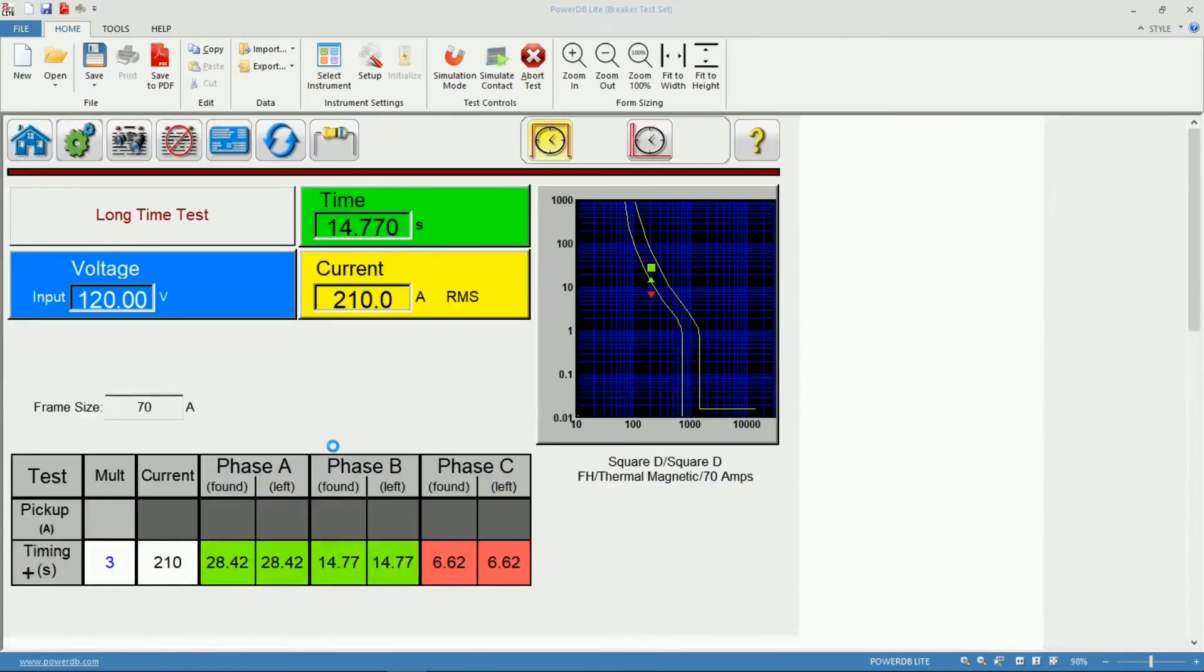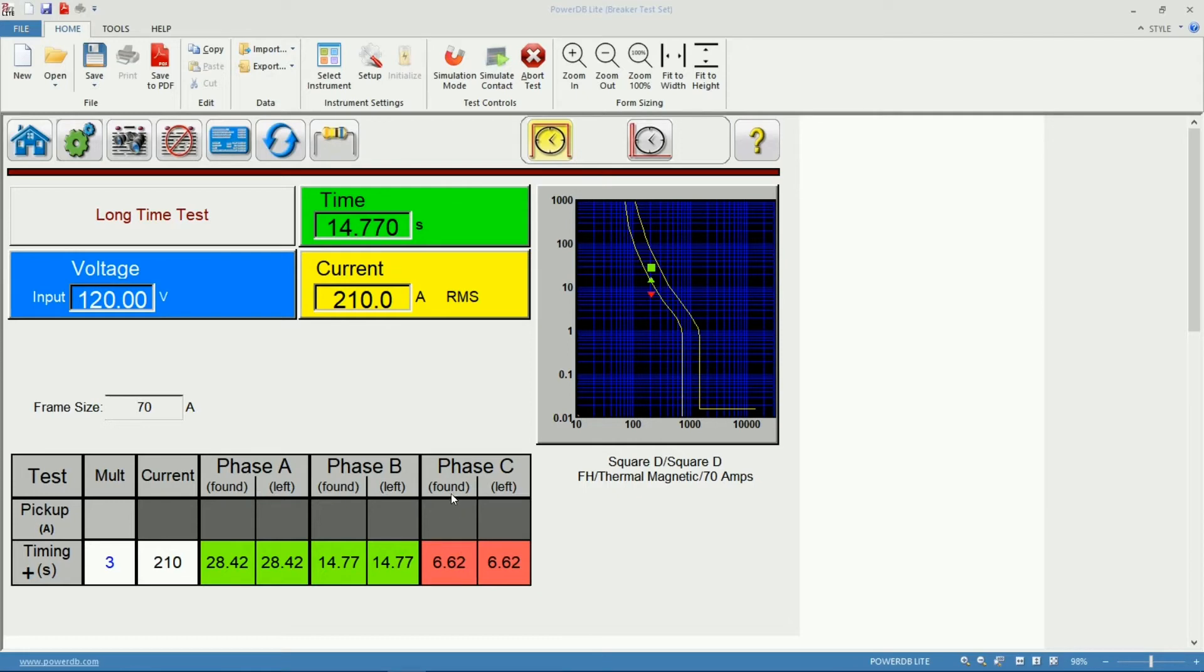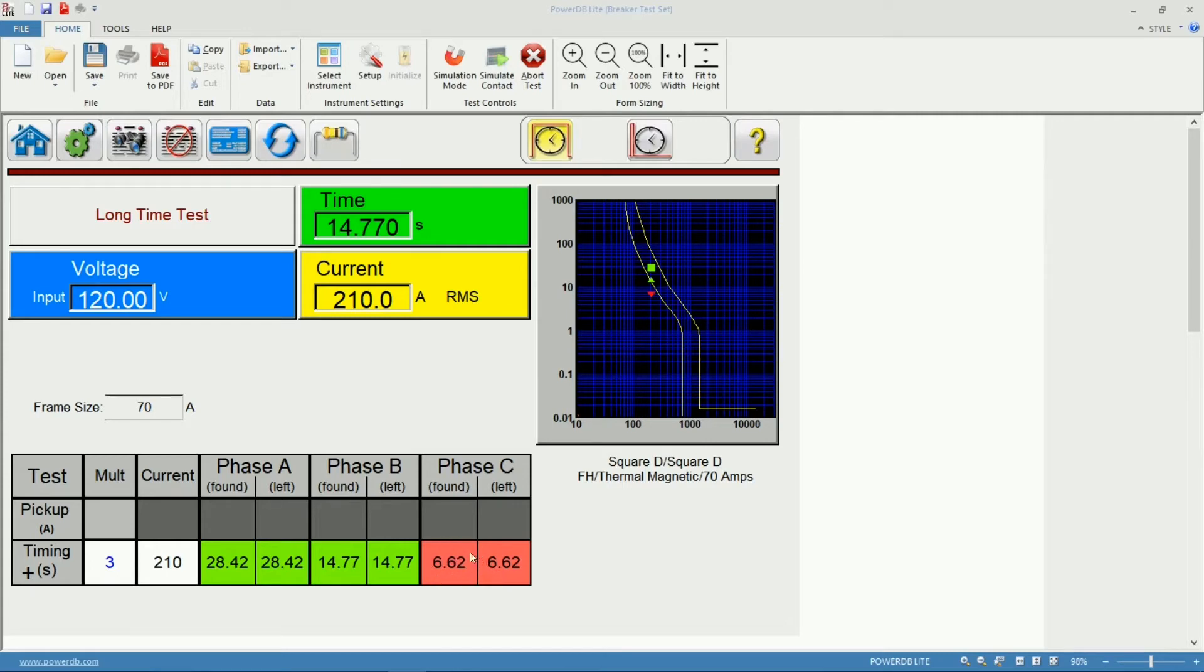Let's say that we did some corrective actions in this circuit breaker and we want to rerun the test to assure that those corrective actions indeed fixed our failed measurement on phase C. For that purpose we have the as found section and the as left, that is the reason we have the two columns for each phase. We don't want to lose our previous result because that will be an important display in the report to tell that we actually performed some corrective actions in this breaker.